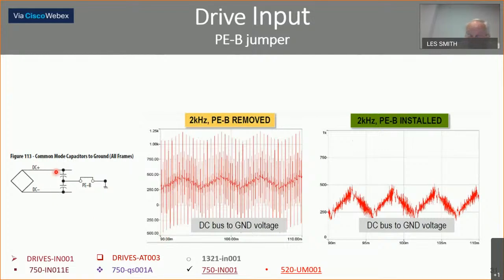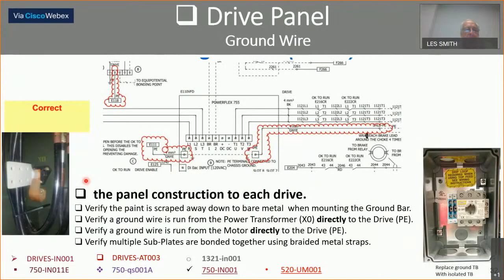The overvolt rating on a drive is 810 volts. Those capacitors have a rating of 800 volts. So what we have is this agitation of the components in that drive all the time, which will cause a shorter life. That's why we like to have a grounded system. Okay, this is our last slide, I think. Right here's our grounding, PE ground here and here.